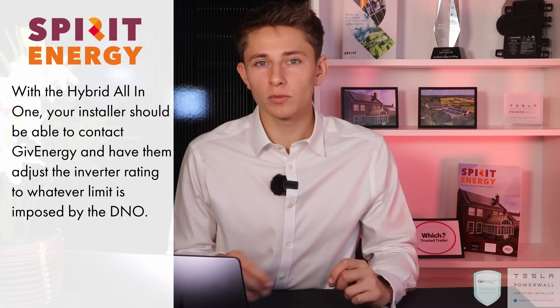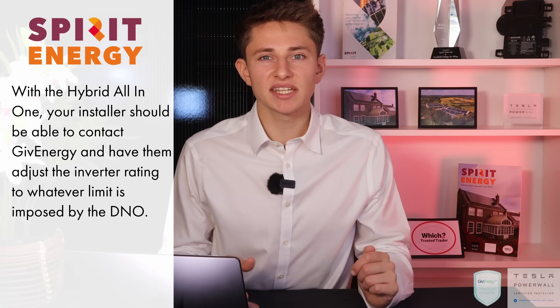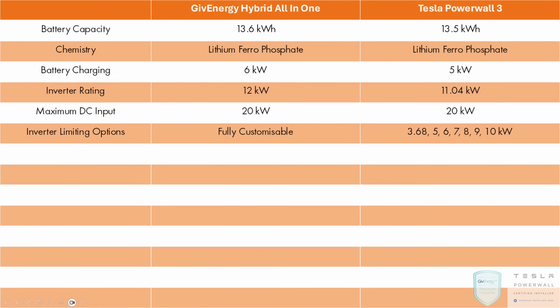The GivEnergy, however, can be limited more precisely. Your installer contacts GivEnergy with the DNO letter and GivEnergy can limit it to precisely what has been allowed. For example, if you receive an offer of 8.6kW, with the Tesla you'd have to round down to 8kW. With GivEnergy, you can limit to exactly 8.6kW, eking out that extra bit of performance from the system.